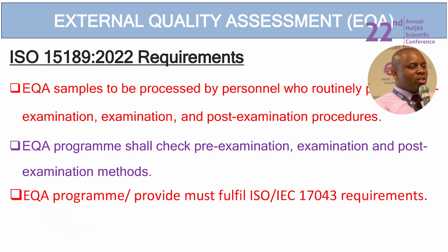The EQA provider that you are looking for should be accredited to ISO 17043, now as a mandatory requirement. You don't want just to have anybody telling you about your performance. How do you check how reliable their report is? Now this reliability has to be confirmed by their accreditation to ISO 17043. This standard is the one that guides on how PT materials should be prepared, how the analysis should be done, the statistical analysis involved, when do you fail a participant, when do you pass them.